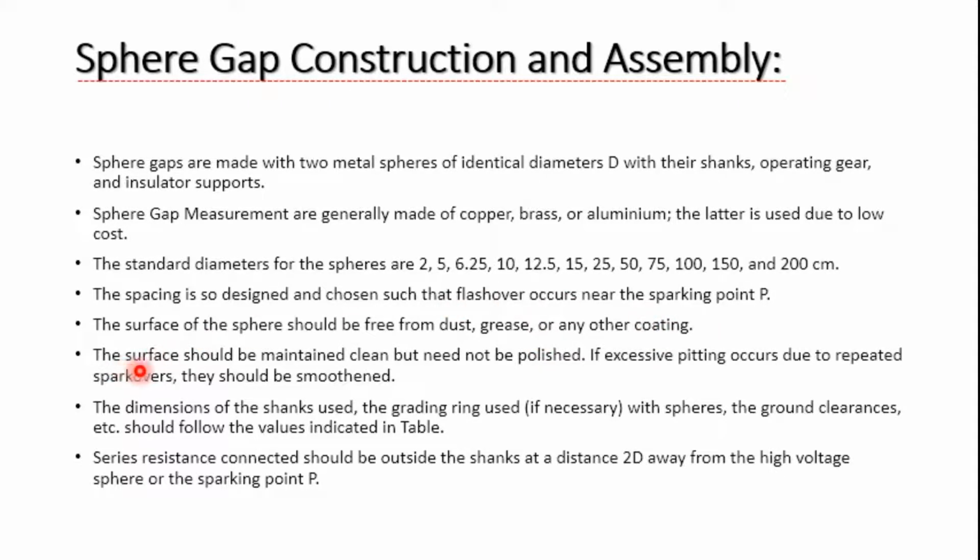Make sure that the surface of the standard spheres is clean but not polished. If excessive pitting occurs due to repeated flashover, they should be smoothened. This care has to be taken for the standard spheres.